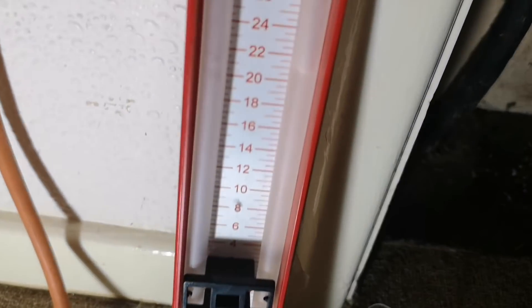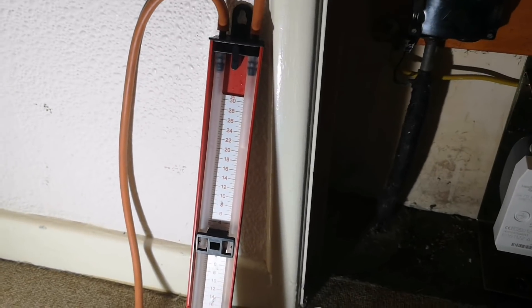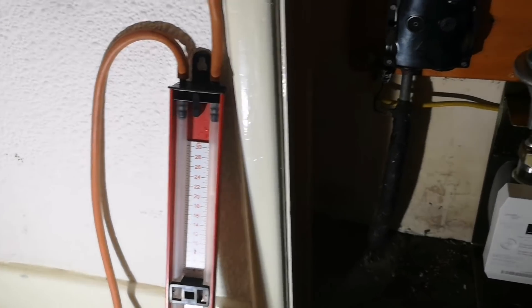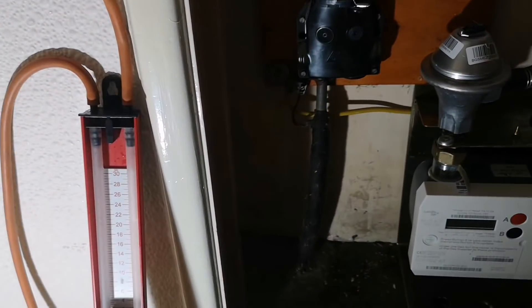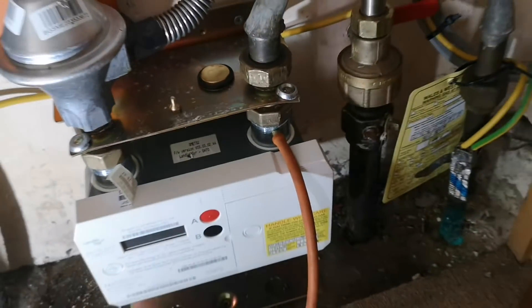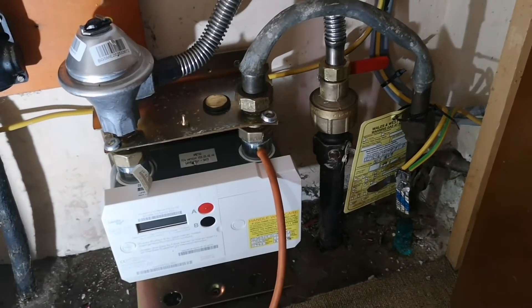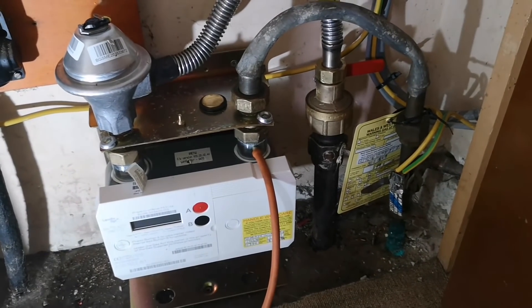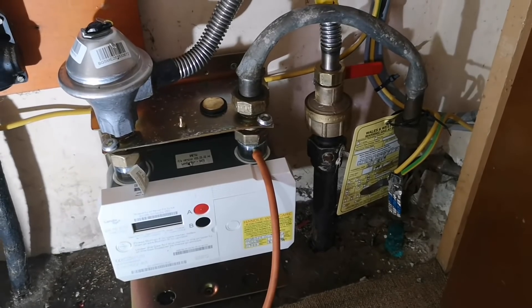We've conducted our soundness test - as you can see there's been no perceptible drop on the water gauge whatsoever over three minutes: one minute stabilization, two minute test. That leads me to believe that either there's still a cap in there and we're only testing this section of meter, or the boiler's been isolated and the leak is on the boiler. I should have checked first but I didn't, so we'll go and check the boiler.